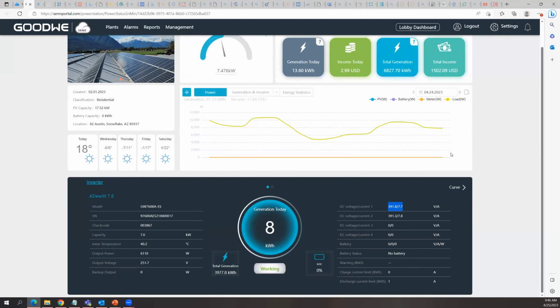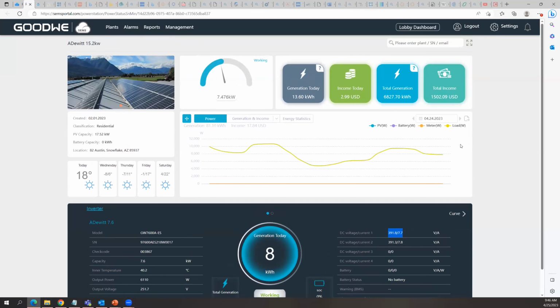As far as the voltage in general, to me, we should be recording all those high voltages, and the inverter at times should go into momentary cessation or something because you've hit an area on the grid settings where you've exceeded for too long a time, and it either goes into cessation or it goes into full trip, depending on it, to protect itself, as it's supposed to do. So I don't know if that answers your question, but at least we're capturing the data.